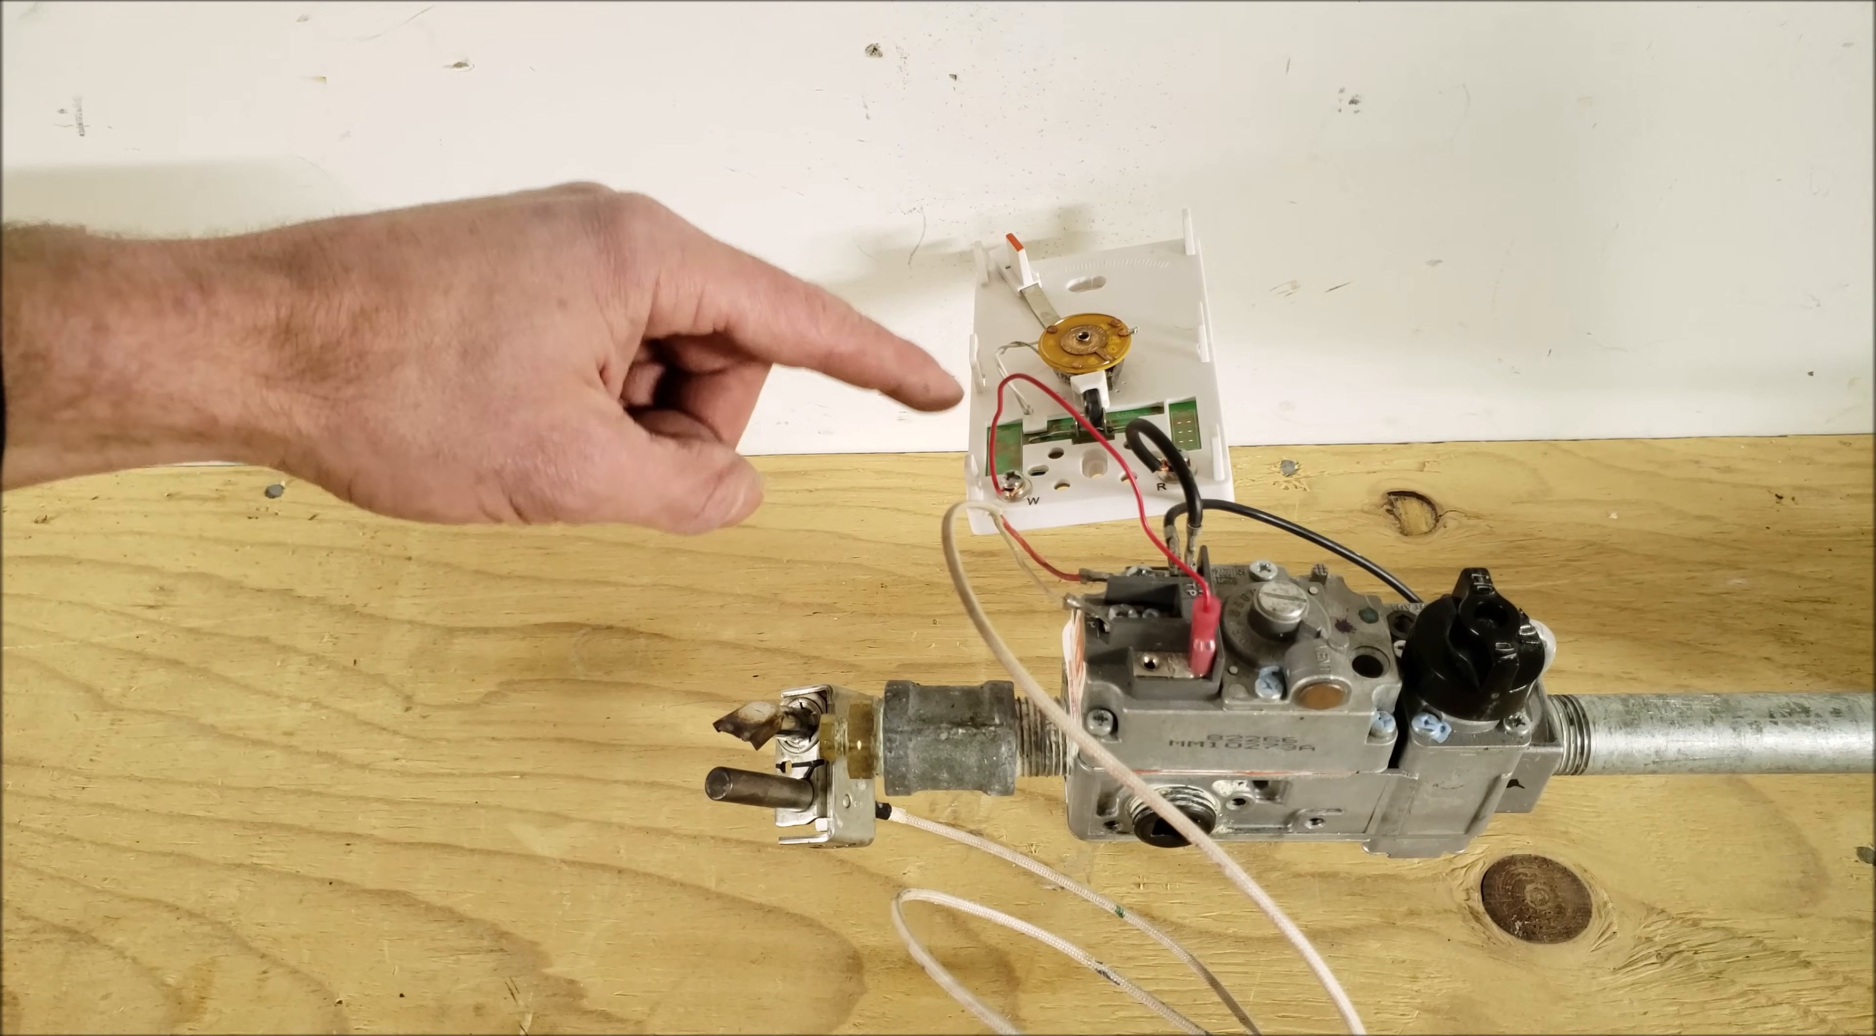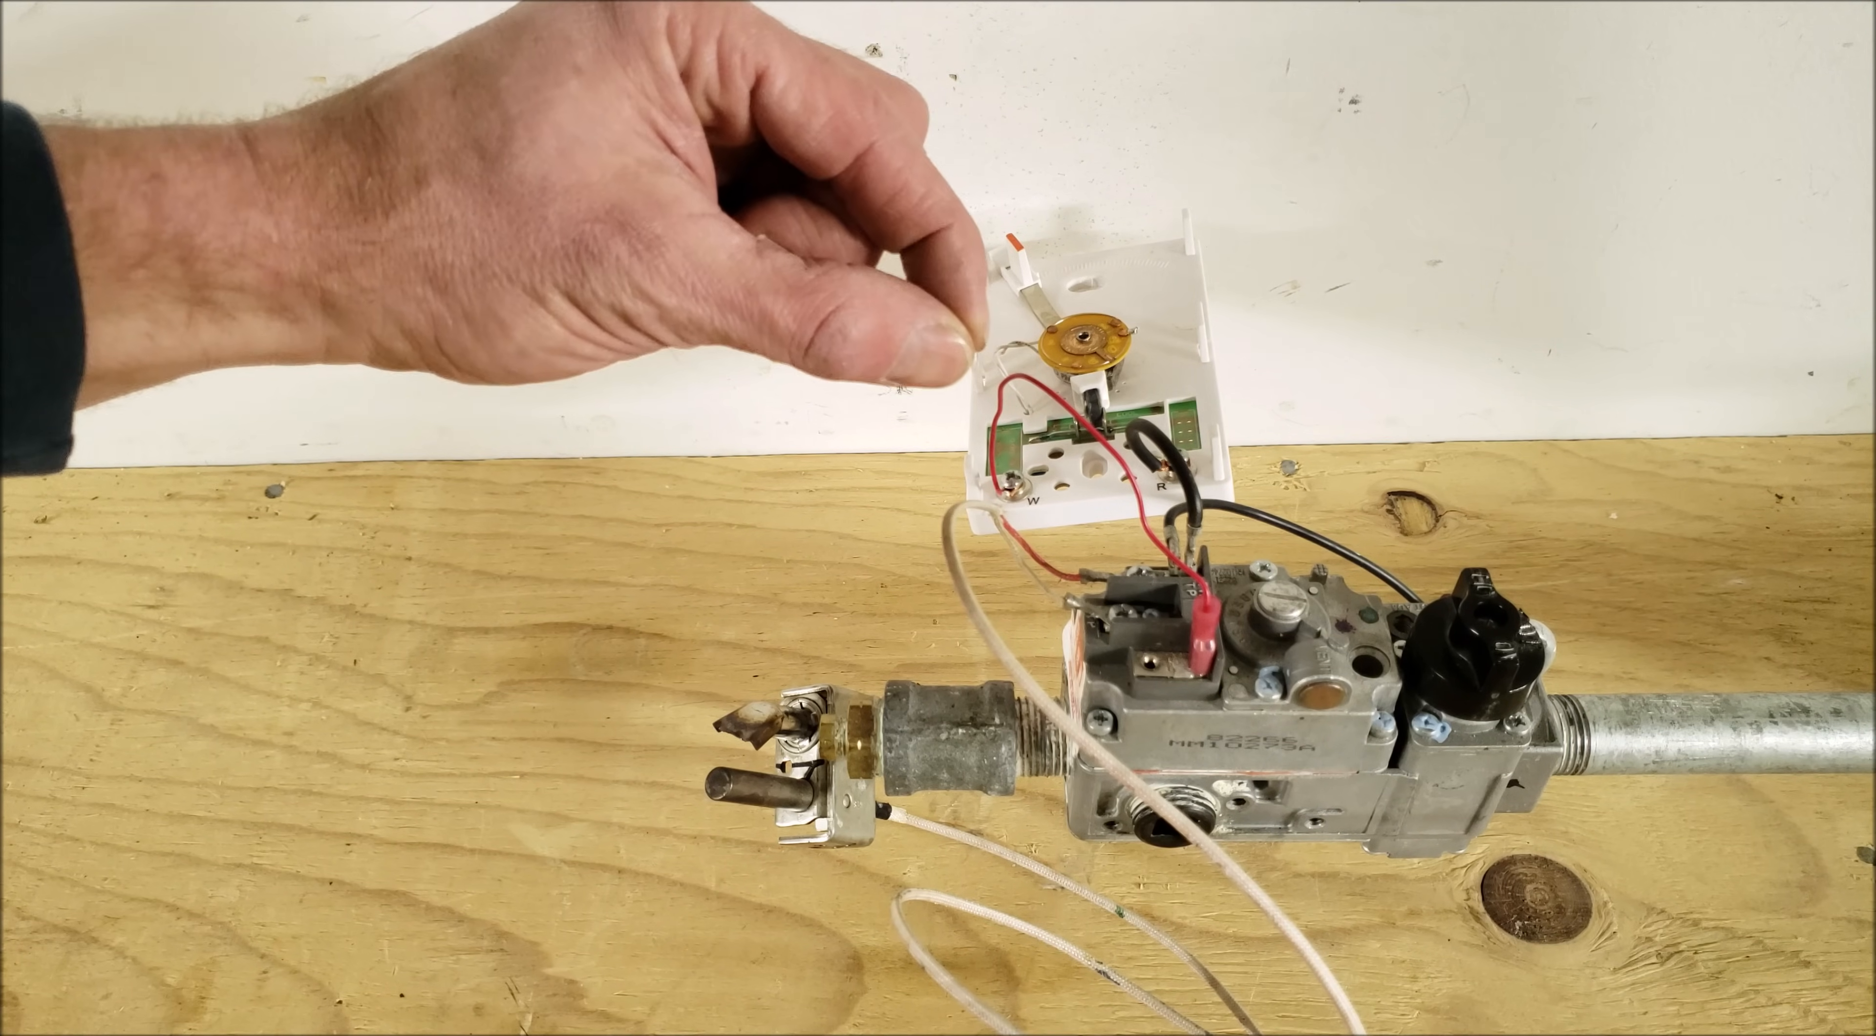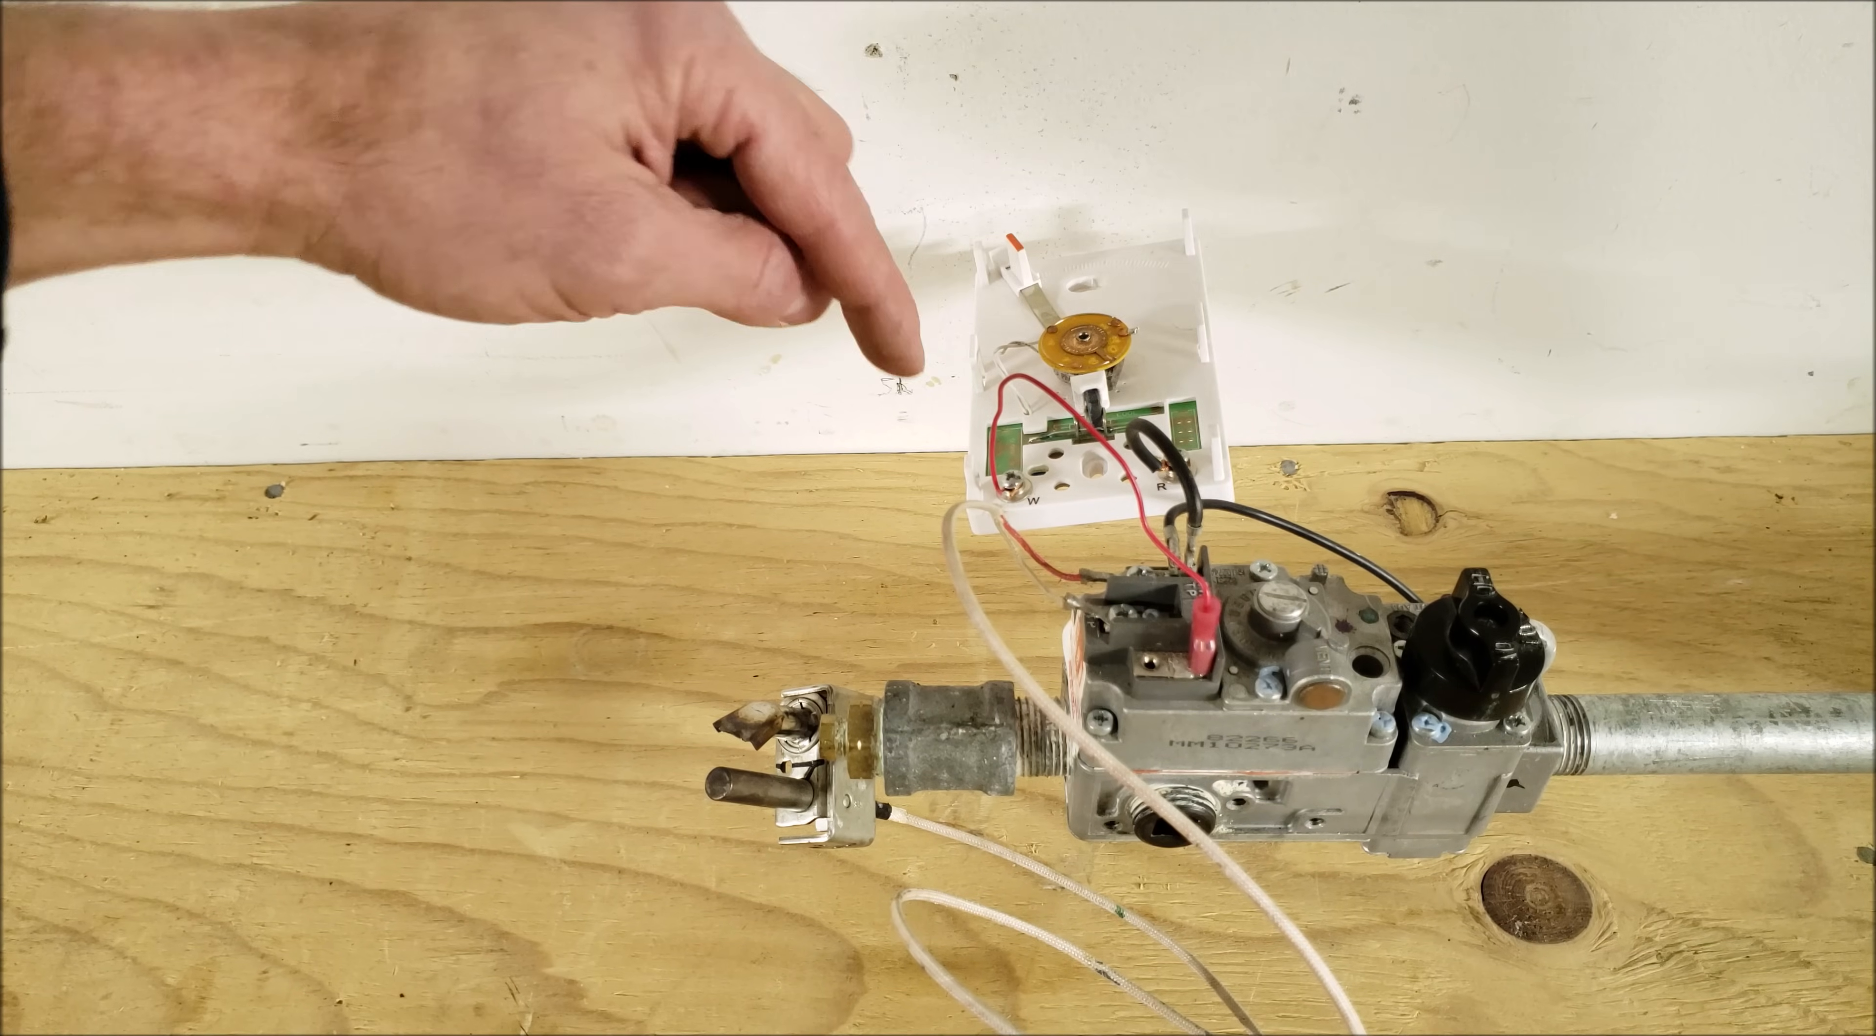Now it's important to use a thermostat that's rated for 750 millivolts because the connection has to be very tight so it can't have any resistance. Otherwise you're going to lose your millivolts and you may not have enough to power the main gas valve.